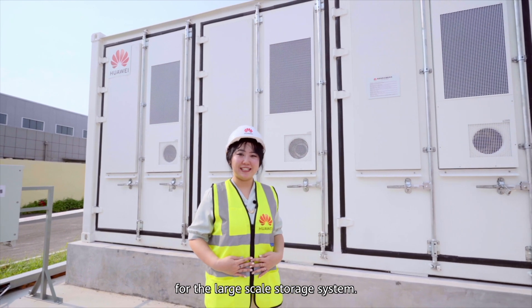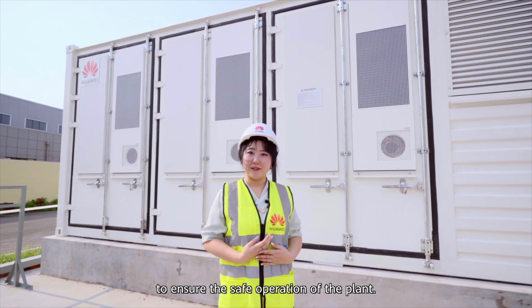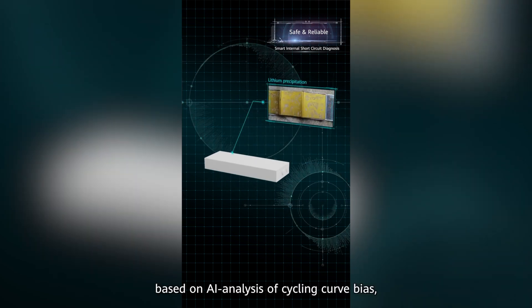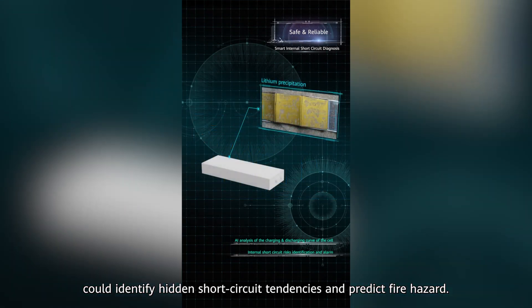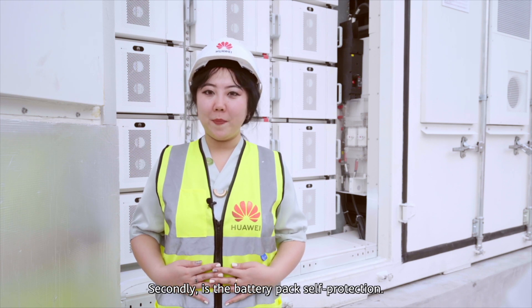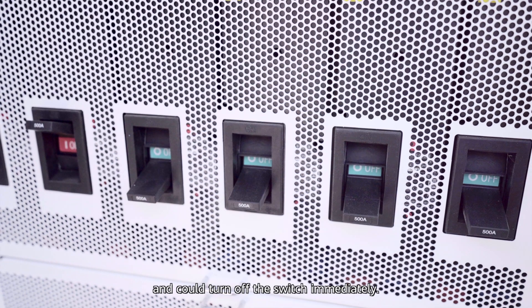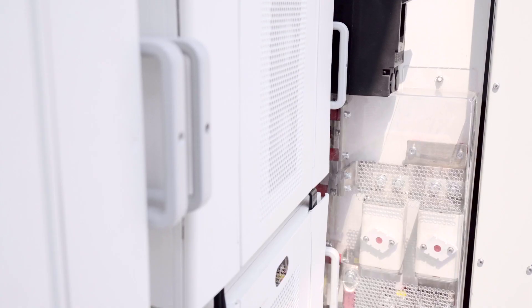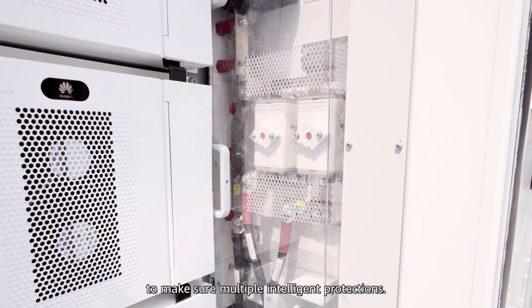Safety and reliability are always the first to be considered for large-scale energy storage systems. We have developed a 4-level safety assurance design to ensure safe operation of the plant. First, smart internal short-circuit diagnosis — based on AI analysis of charging curve data — can identify hidden short-circuit tendencies and predict fire hazards. Second, battery pack self-protection: the battery pack optimizer isolates the battery pack and can turn off the switch immediately. Third, the battery rack can shut down the system actively to prevent fault spread, with circuit breakers and fuses isolating two-level faults to ensure multiple intelligent protections.